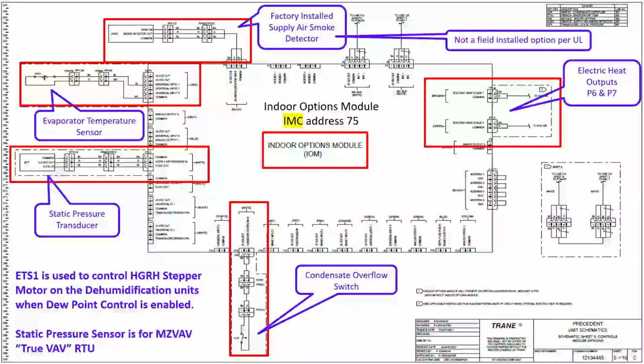Indoor options module is for heat strip. Factory installed smoke detector. So if you have a supply air, sorry, this is for supply air. The return air plugs in on a different board. So if you have your evaporator temperature sensor, static pressure transducer, condensate overflow switch, this all comes off of our indoor options module. Here's our electric heat inputs, P6 or P7.